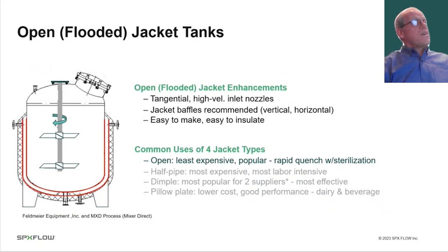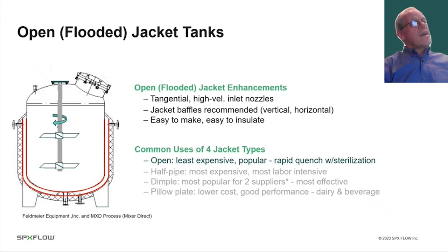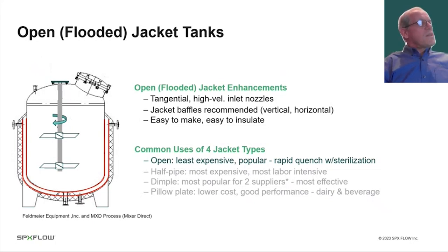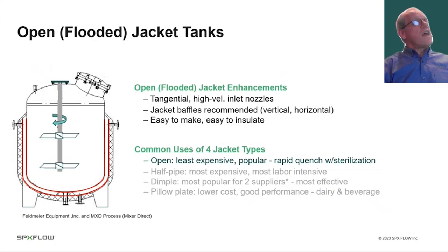The open or flooded jacket is essentially a vessel nested inside a larger vessel, with the annular space flooded with heat transfer fluid. You can add enhancements such as high-velocity inlet nozzles to increase the heat transfer coefficient, and vertical or horizontal baffles to control flow and avoid short-circuiting. This is the least expensive type of jacket and is common for applications like rapid quench with sterilization.